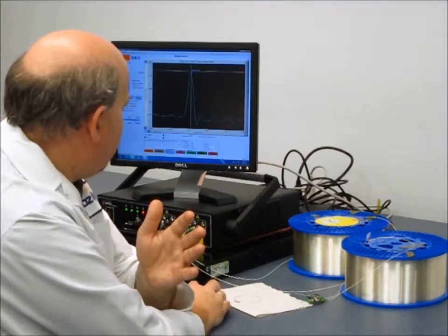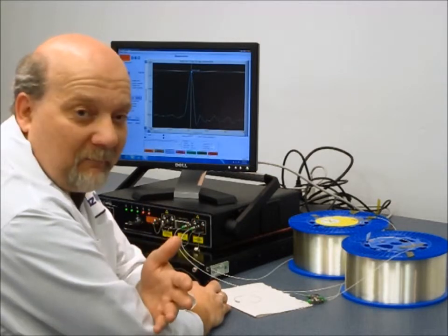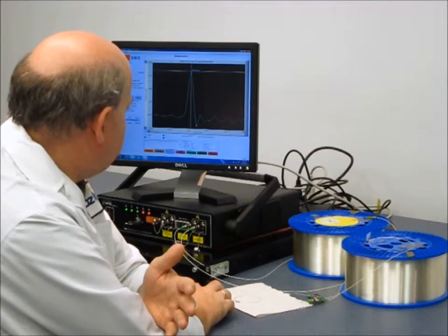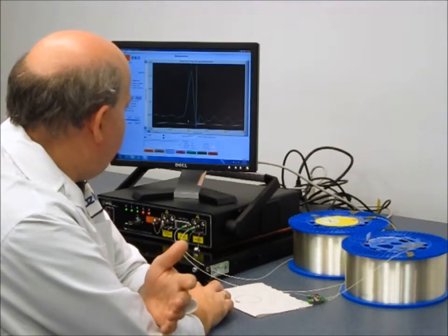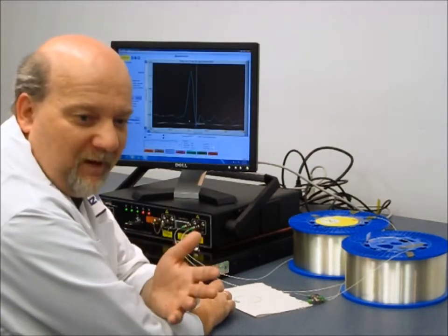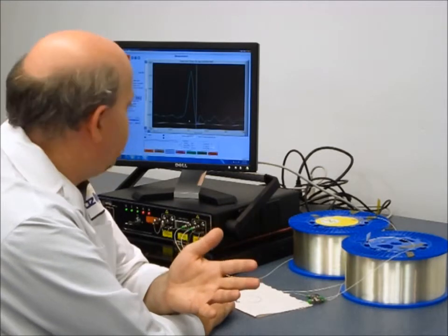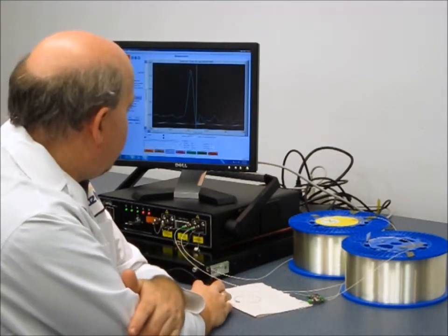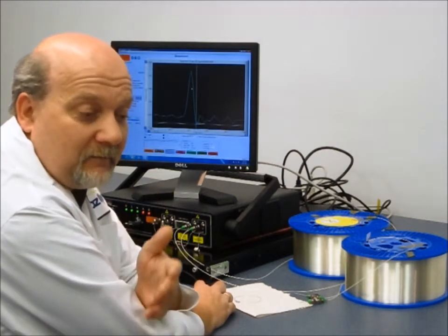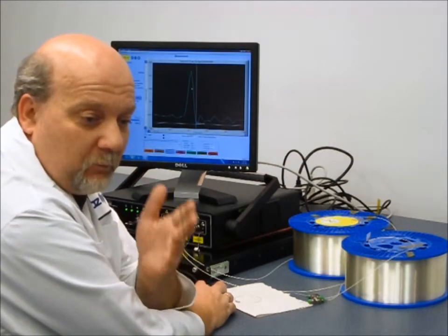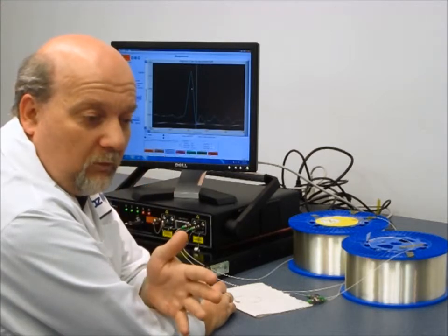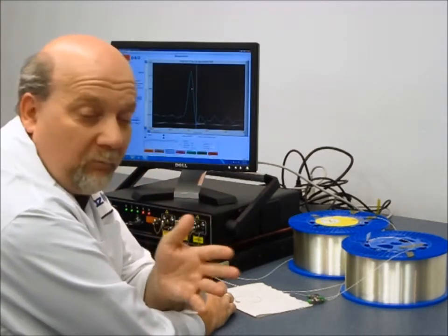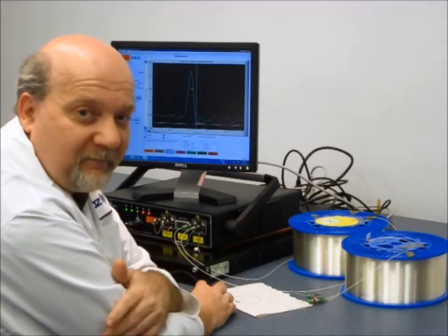And again, going from the 25 kilometers and 42 meters down to 25 kilometers and 45 meters, again about 3 meters, we're back to our zero reading. So this shows that we can detect the changes in temperature with 2.5 meter resolution, over a 50 kilometer length of fiber.